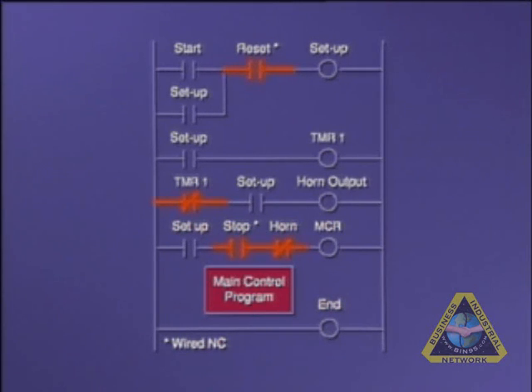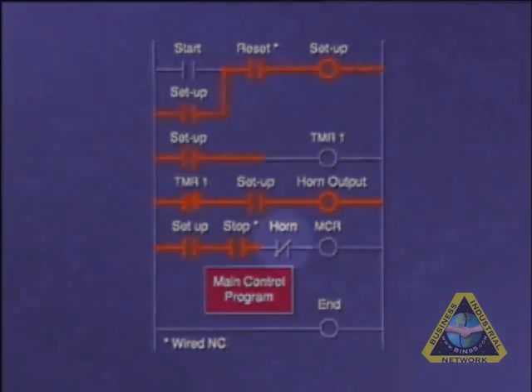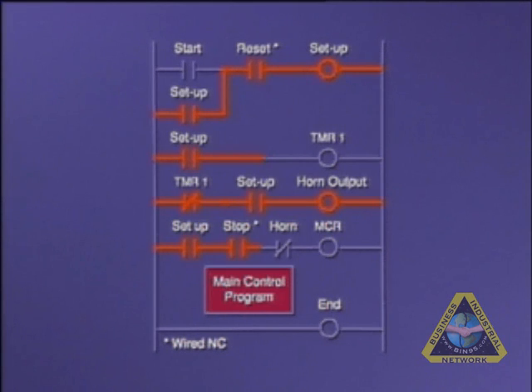If the start push button is pressed, the horn will start sounding. At the same time, the normally closed interlock contacts of the horn output will disrupt continuity for the MCR rung, where the processor will jump all the fenced instructions all the way to the end MCR.